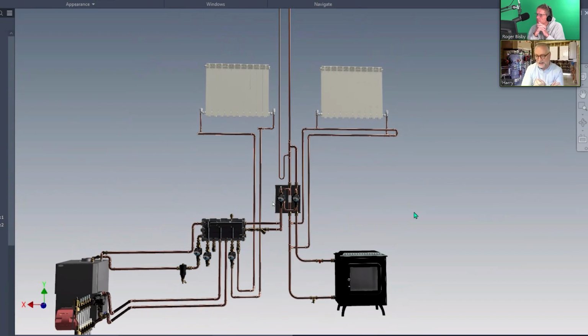Yeah, it's basically methane, you set fire to it. But what it is, is organic growth within the water fed by the oxygen. If there's no oxygen in the water, you can't have life, and the life can't cause issues. When the oxygen's getting in, it attacks the ferrous parts and causes rust. So when you fill a system up, you're going to have a bit of free oxygen in there.